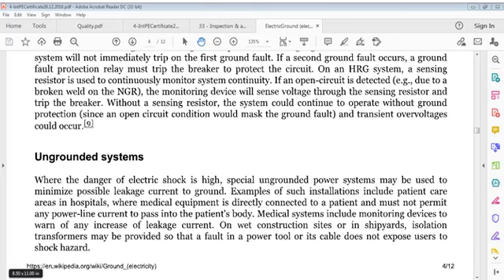Ungrounded systems, where the danger of electric shock is high. Special ungrounded power systems may be used to minimize possible leakage current to ground. Examples of such installations include patient care areas in hospitals, where medical equipment is directly connected to a patient and must not permit any power line current to pass into the patient's body.